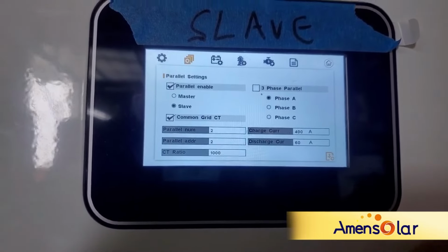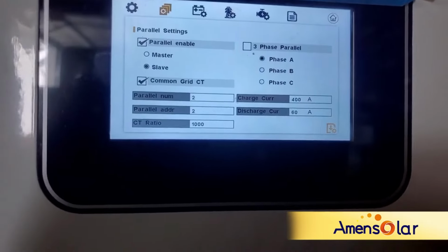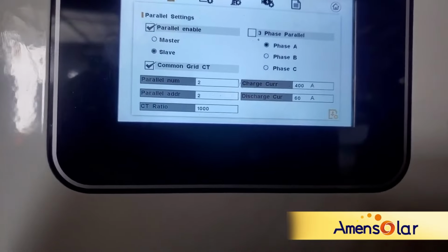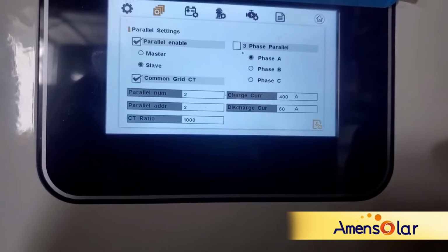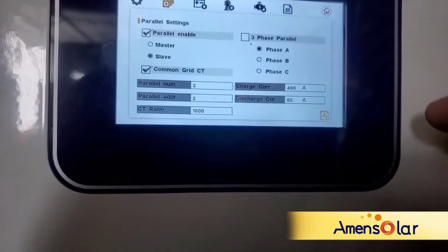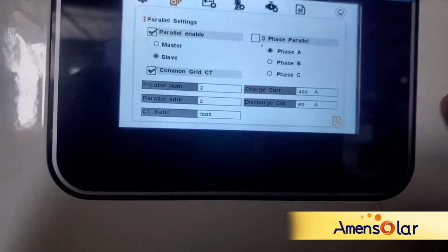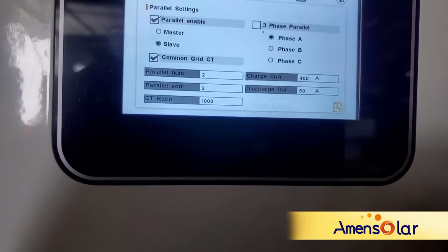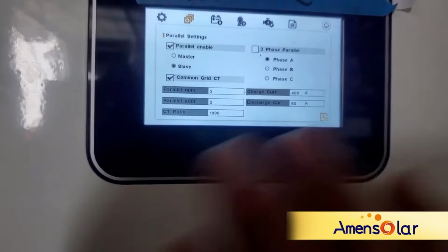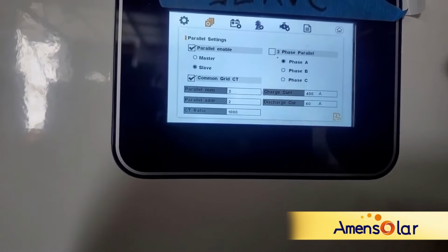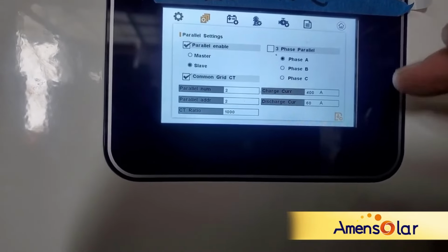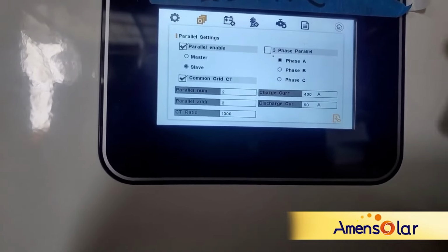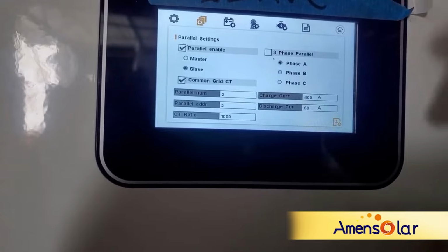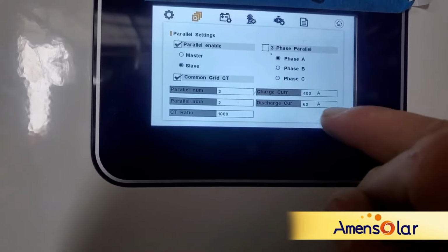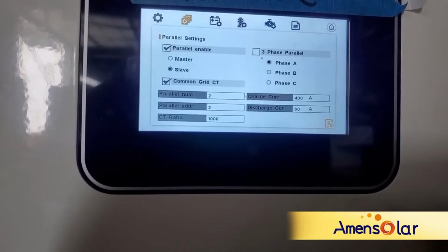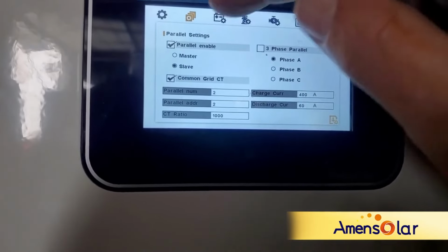In other words, if you don't want to over discharge your batteries at any particular point, you can set the maximum limit for discharging amps. It says 60 amps at this stage. 60 times 50 volts is about 3 kilowatts per unit, so that's 6 kilowatts in total. And if we pull any more than that, then it's going to supplement from the grid, if the grid is available. If the grid's not available, this will be ignored. It'll just give all it can until the batteries cannot anymore.